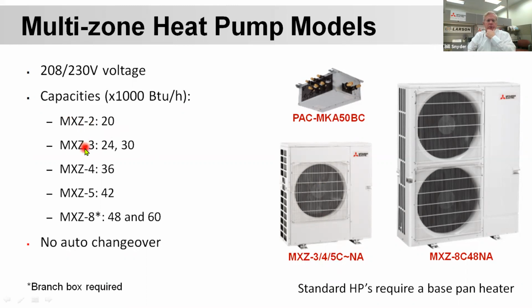And then there's a 3-zone, with 3 ports on the outdoor unit, 3 ports on the 24 and 30, 4 ports on the 36, 5 ports on the 42, and on the MXZ-8C48 or 60, the 4 and 5 ton units require a branch box. This branch box number with the 50 in there would indicate it would be 5 zones. This picture shows 3 zones. There's a high and a low side. There's 3 sets there, just to give you an idea.